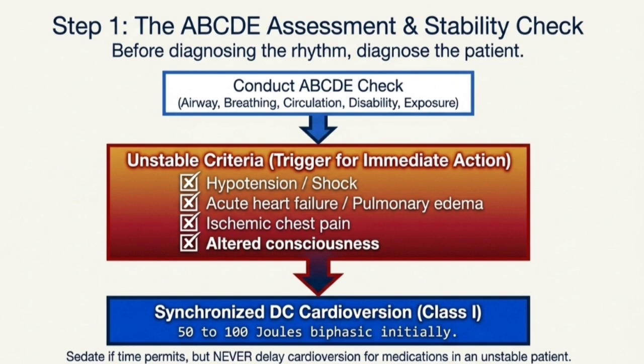Well, first off, we use a starting dose of 50 to 100 joules with a biphasic defibrillator. Okay, 50 to 100 joules. But the synchronization part, that is the difference between saving the patient and literally causing a lethal arrhythmia. Wait, really? Lethal? Yes. When you hit the sync button on the machine, the defibrillator reads the patient's ECG on the screen, and it places a tiny marker on every single R wave. The R wave being the tall peak of the heartbeat, right? The ventricular contraction. Exactly. So when you press the shock button, the machine doesn't just fire instantly. It will actually wait a fraction of a second to deliver the electricity exactly on that R wave.